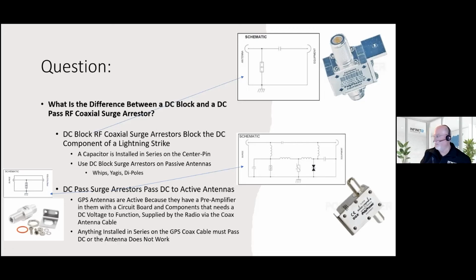So if your antenna needs 5 volts, you don't want to put a 60 volt thing on it, because it would pass the 60 volts. That's too much. We actually make a 6 volt and a 15 volt that lets through much less voltage to your receiver. So use the right surge arrestor for the right antenna voltage. So in the DC pass world, this is the premier one with everything. This is a straight gas tube design that's also DC pass, because there's no capacitor on the center pin there. It's just a wire. But this is good. This is best.